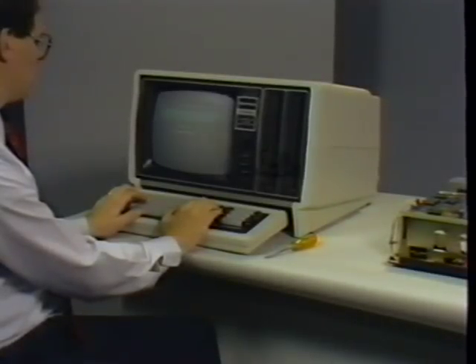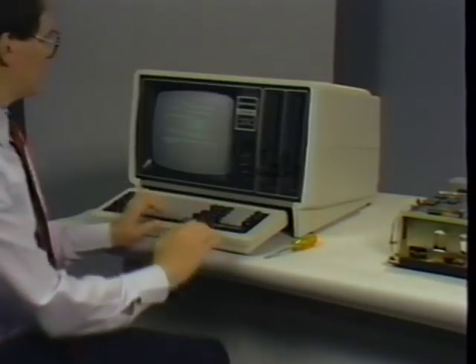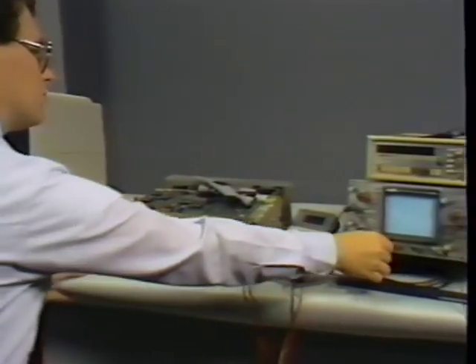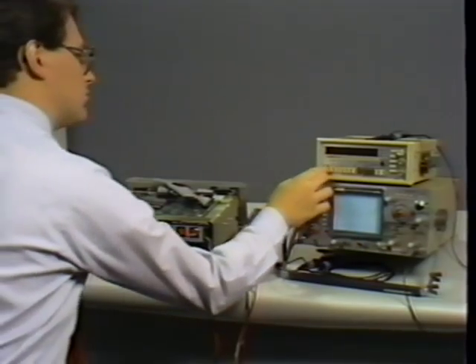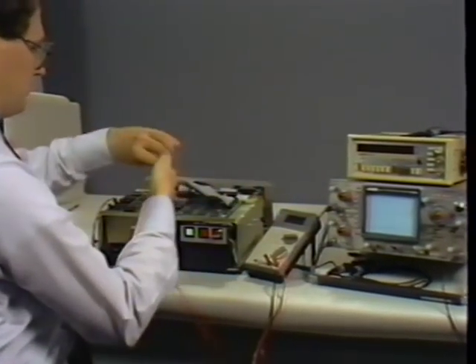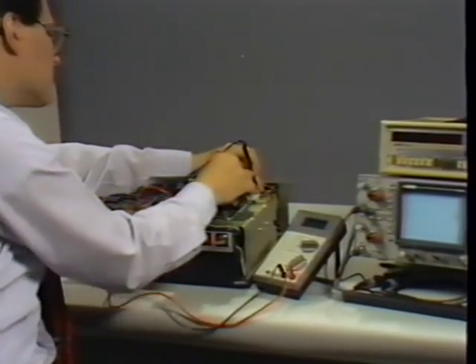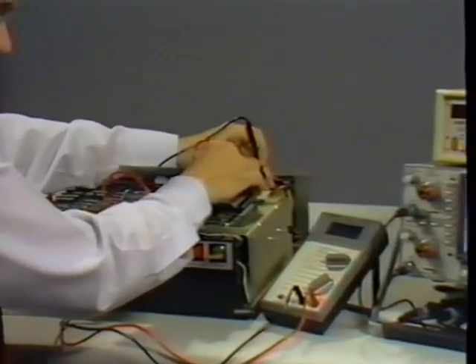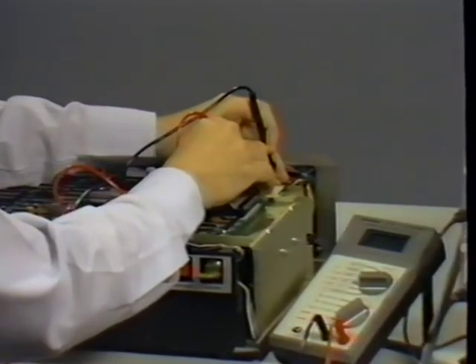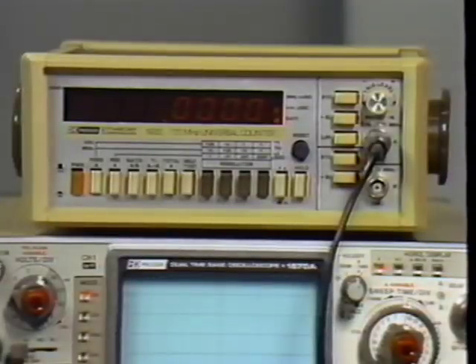While waiting for the bubble to warm up, run all interface and controller diagnostics. Also, warm up your scope and frequency counter and check and calibrate your probes. Check the power supply voltages on each drive. The measured output must be at least the specified value. Measure the noise on each power supply with your scope. Consult the service manual for the acceptable range.